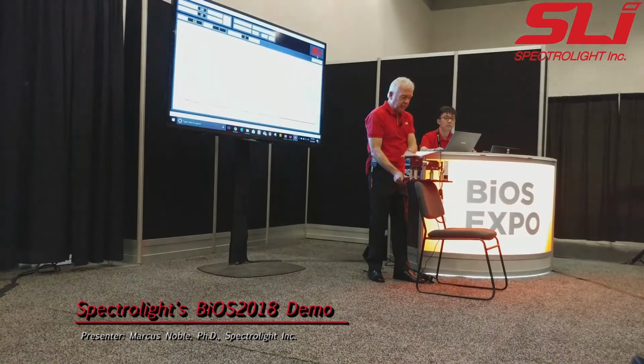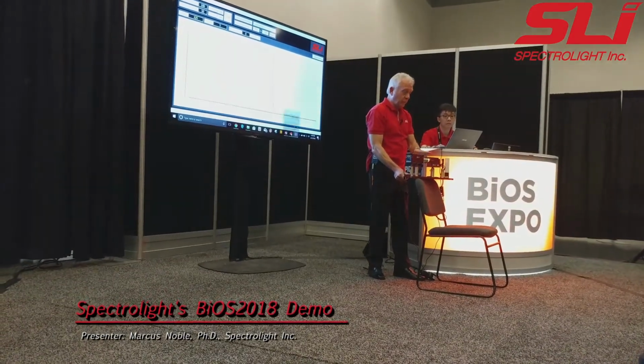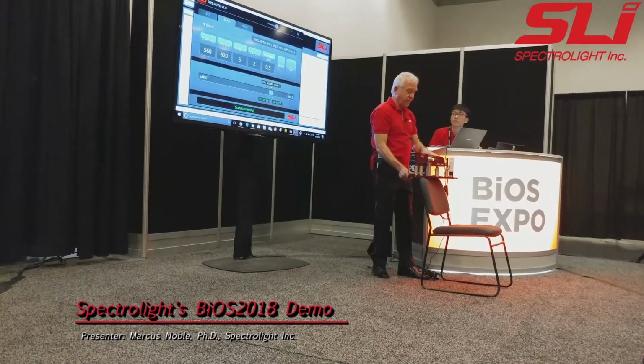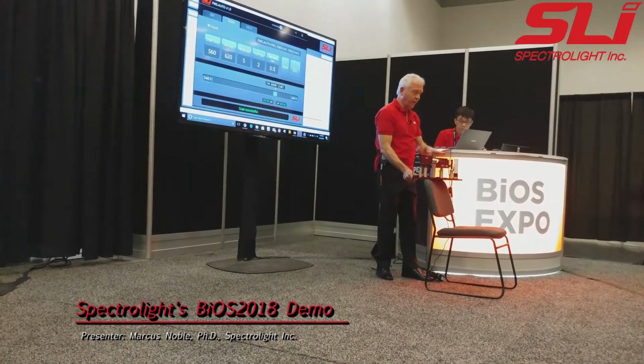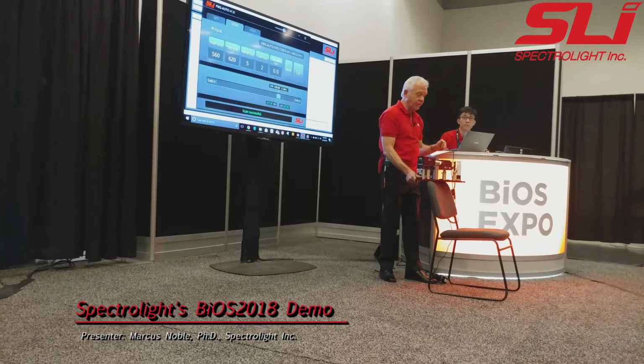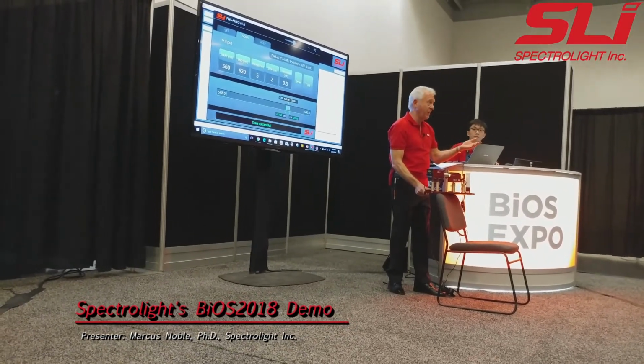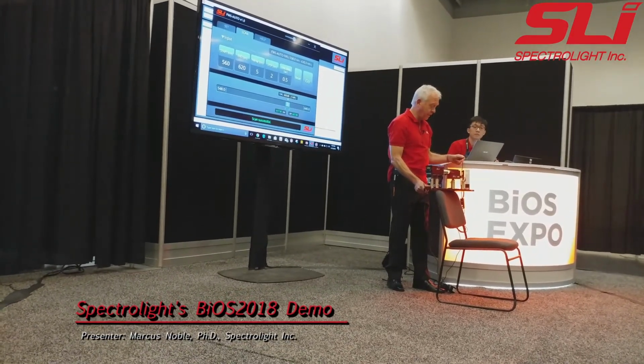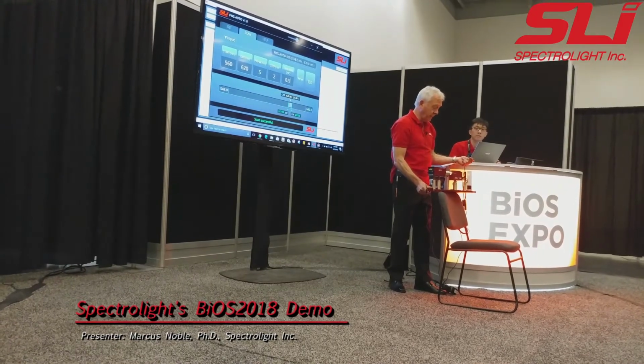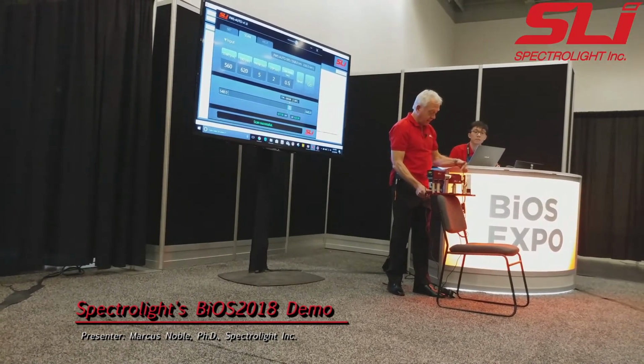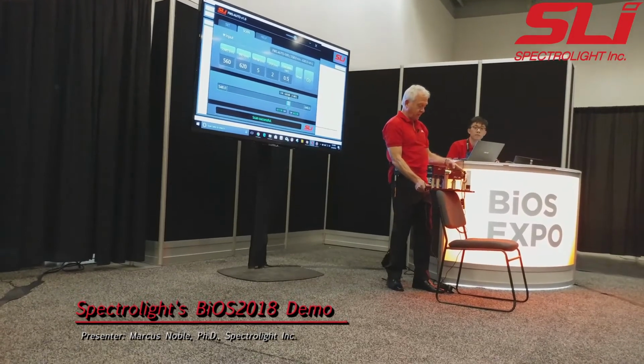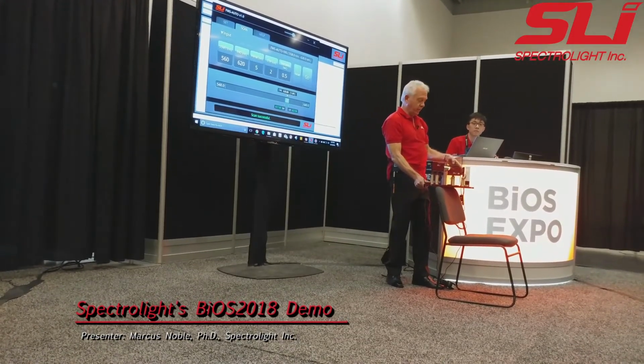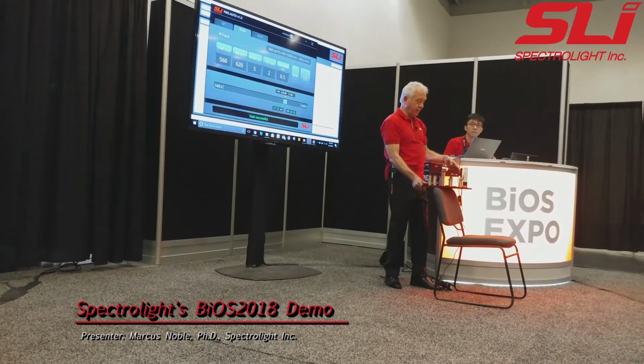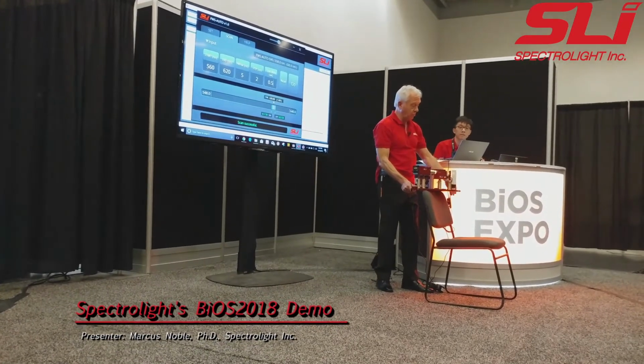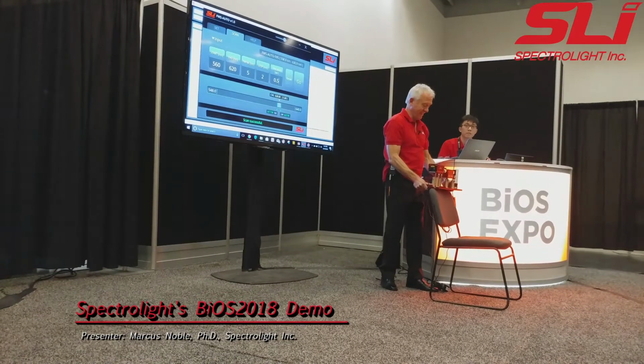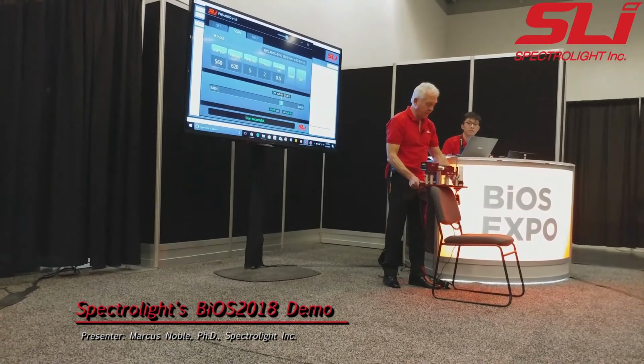We've got a white light here. It's collimated. That's an important distinction of this device. It's got to have collimated input and output, which is fine in a microscope. Obviously, the infinity space is a prime spot for this in a microscope where the light is already fully collimated. I've got a beam split here, sending part of the light into one of our spectrometers, 2048 array spectrometer, and I've just put this little white screen in so you can actually see the wavelength.